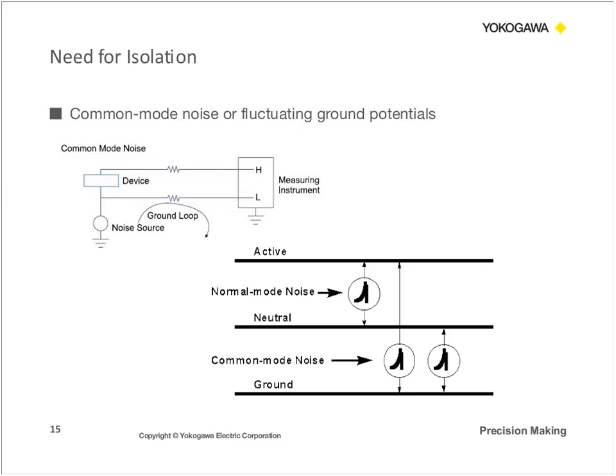This makes sense for large industrial plants or for enclosures that are already pre-built, and you're not able to go in and modify any of the equipment, or if it's not cost effective, then you should look at how isolation can be used and placed in between not only the device and the measuring instrument, but potentially also between the device and the power line to eliminate the ground loop. And really, the noise can be separated into two different categories, which we will take a look at later. You have your normal mode noise as well as your common mode noise. And you could be dealing with one or both. So we'll be taking a look at how to solve these issues later on in the webinar.